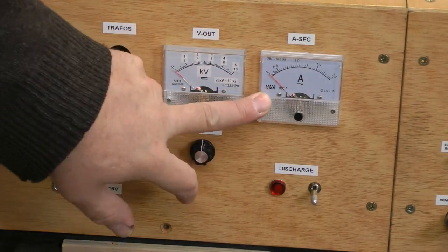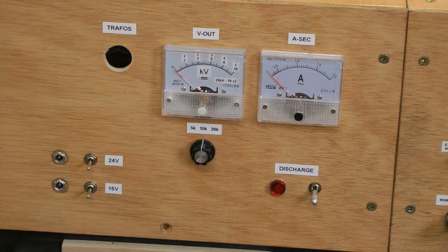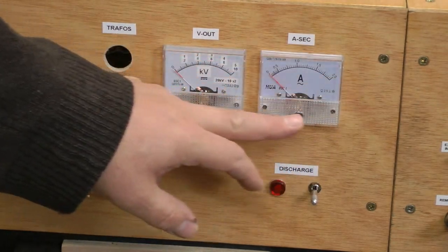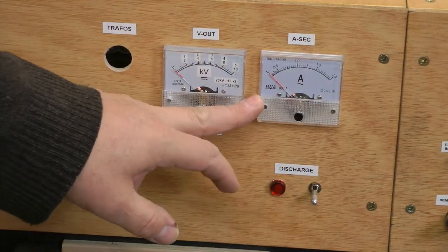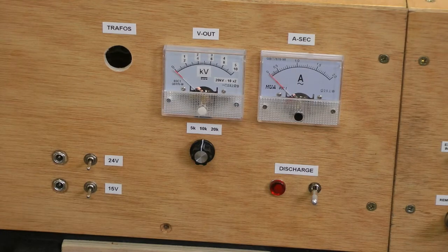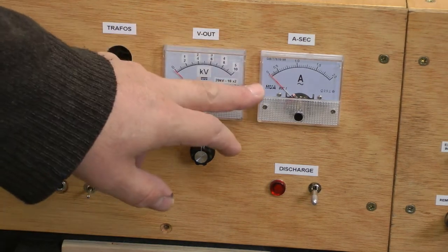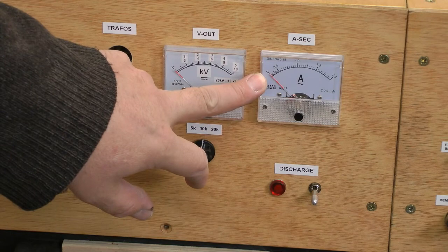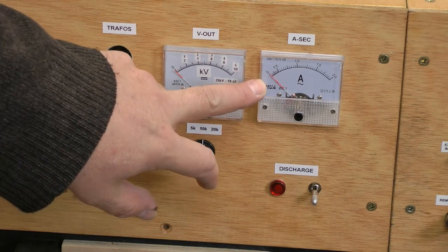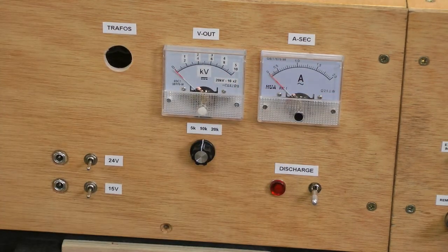So this is actually the current in the secondary. However you got it connected, whether it's in parallel or in series, the lower leg of that passes through this meter, so we can see how much secondary current is flowing. This is an AC meter, because we're obviously running the secondary at 50 Hertz, coming out of the transformers. This is a UK line supply, and this goes from 0 to 2 amps.